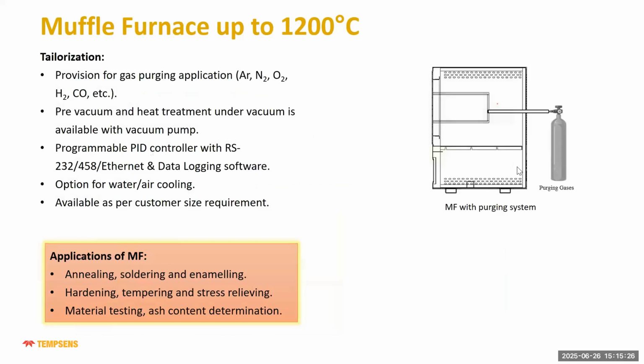We can also do customization of the muffle furnace. If you want argon, nitrogen, oxygen or hydrogen gas purging, we can provide pre-vacuum or heat treatment under vacuum with a vacuum pump, if required. A programmable controller and air cooling can be provided, and customer size requirements can be met. Basic applications of the muffle furnace are annealing, soldering, enameling, hardening, tempering, stress relieving and metal testing.